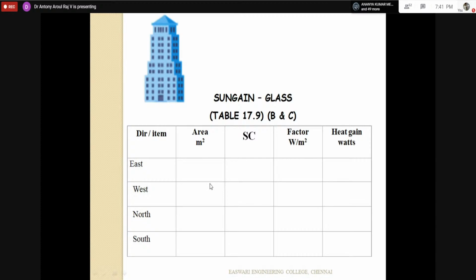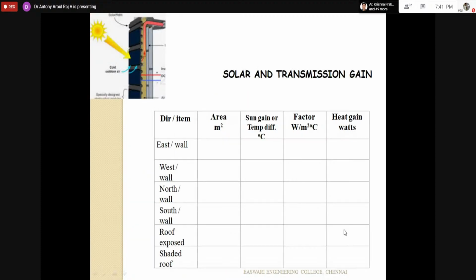So now it is area into SC factor, and another thing is the watt per meter square, for various latitudes, which we just saw. I multiply to get the heat entry - sensible heat entry, the solar and the transmission gains. For transmission gains, it is the wall - all directions, even roof and floor, I have to take into account.